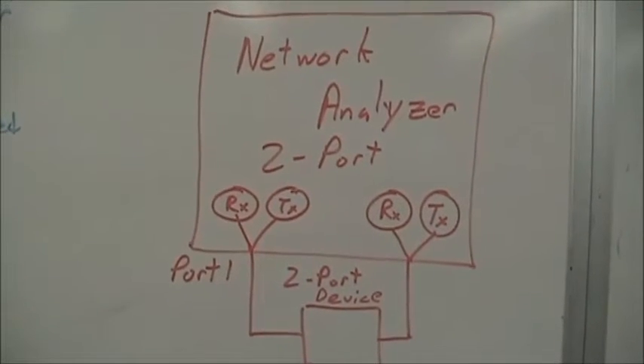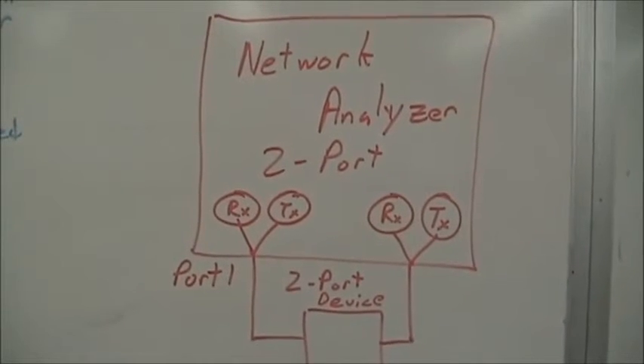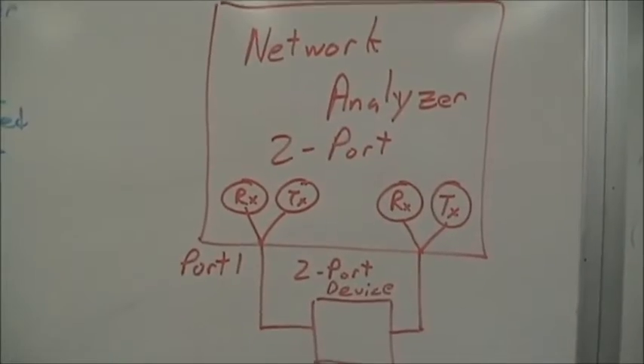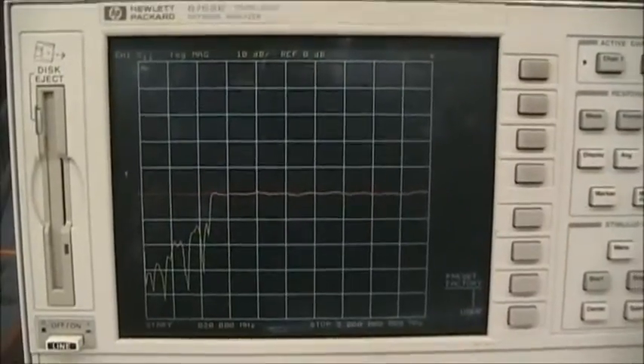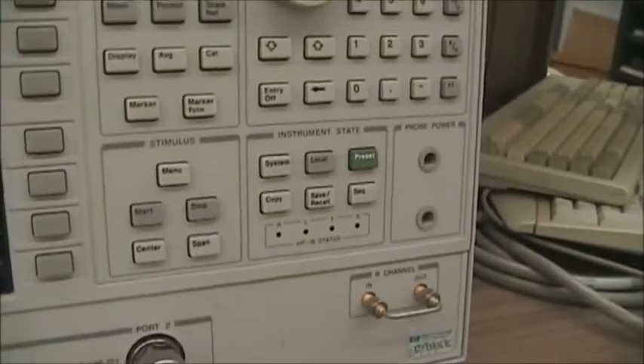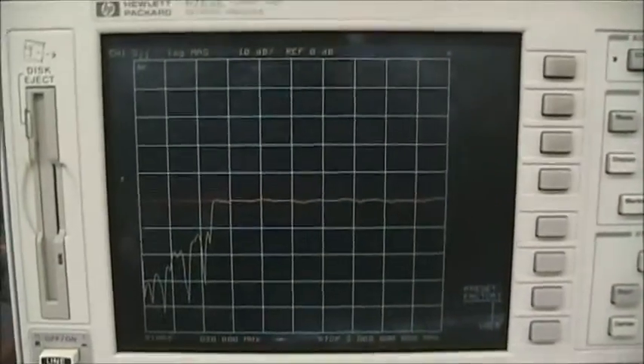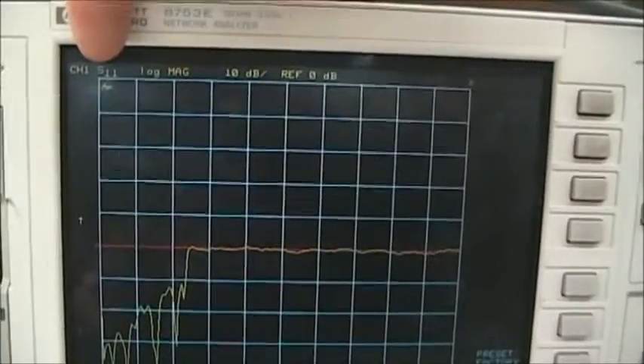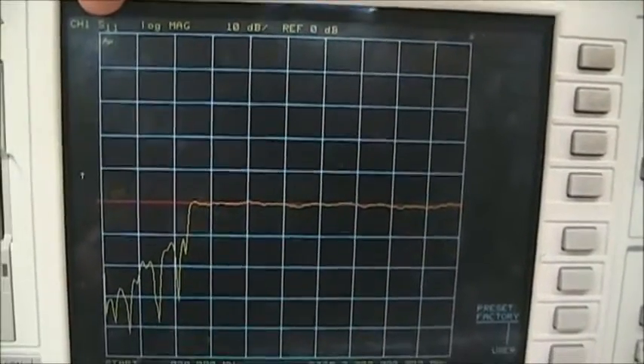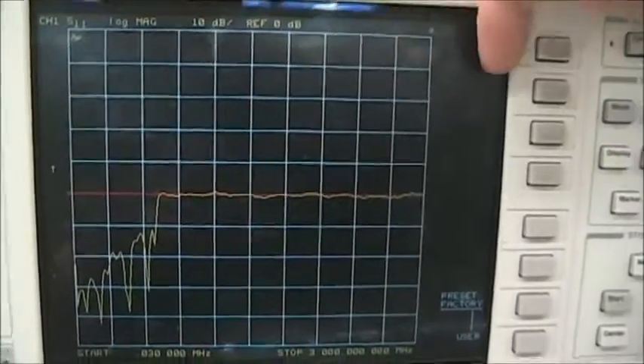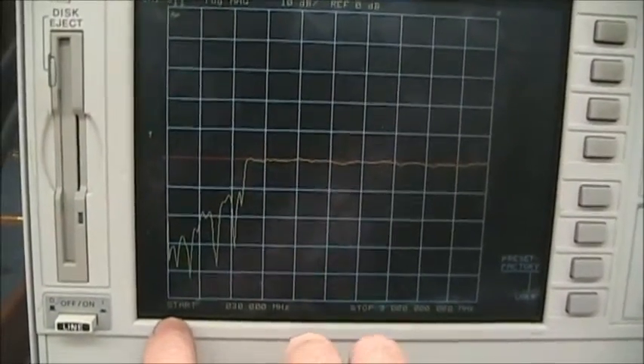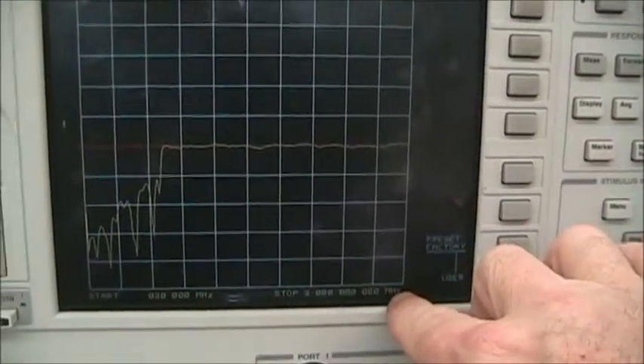Because there are two ports active, we must account for the interaction between the two ports in the calibration process. Upon starting the network analyzer or pushing the green preset button, we have the familiar display of S11, the input port parameter, reflection coefficient, and the frequency range from 30 kHz to 3 GHz.